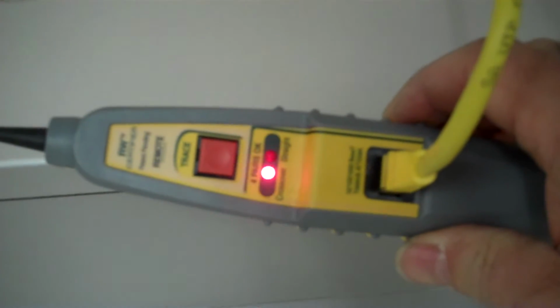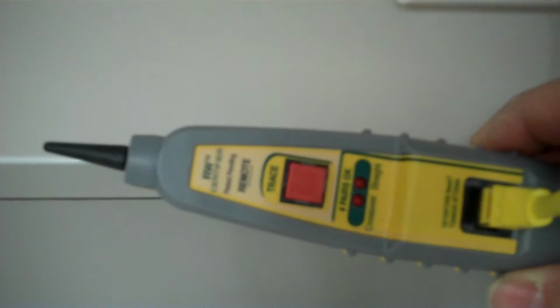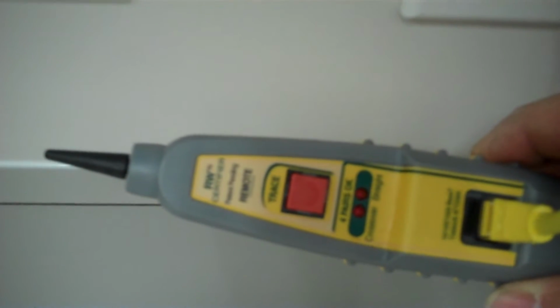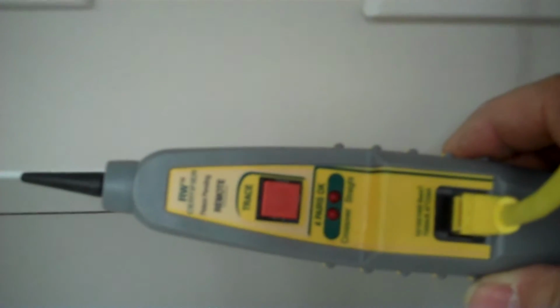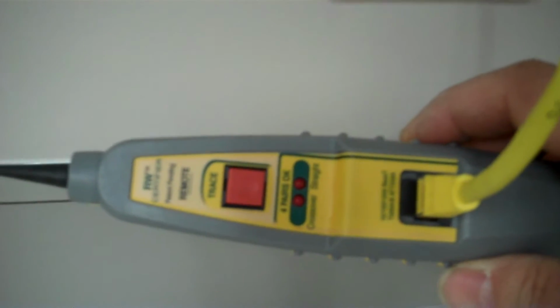Anyway, you plug it in and you'll see the LEDs go back and forth. If the test is successful, it will stop and give you a solid OK light, meaning the test is done and passed. This one was not successful, so let's go look at another one. That test failed due to a map error, so chances are either the patch panel or the jack is punched down incorrectly.